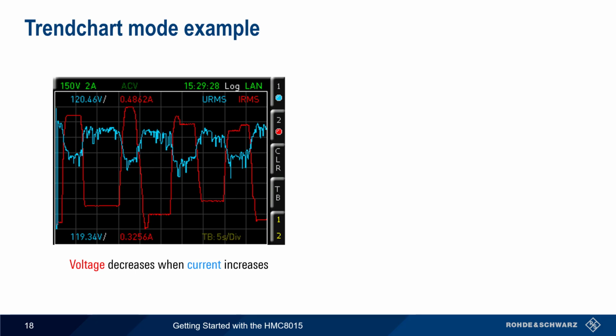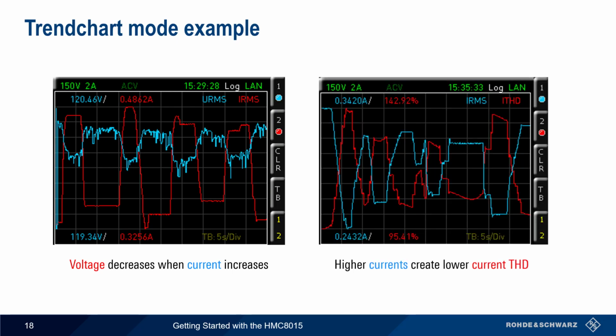Let's look at two examples of Trendchart mode results. In the first example, we see that voltage, the red trace, drops when current, the blue trace, increases. In the second example, we're looking at current and the total harmonic distortion of current, and we can see an inverse relationship. Total harmonic distortion decreases when the current increases.